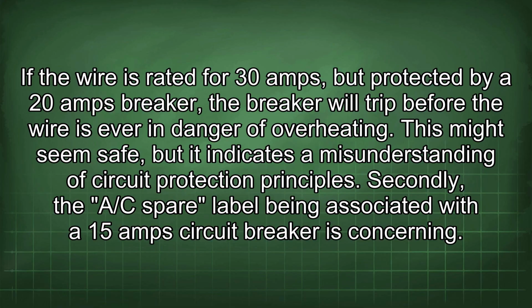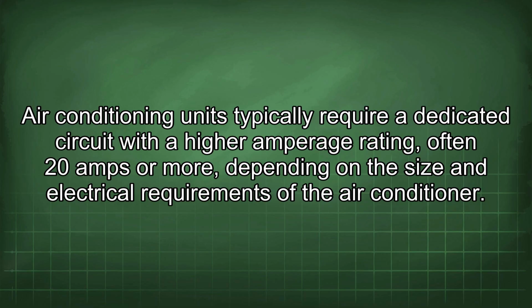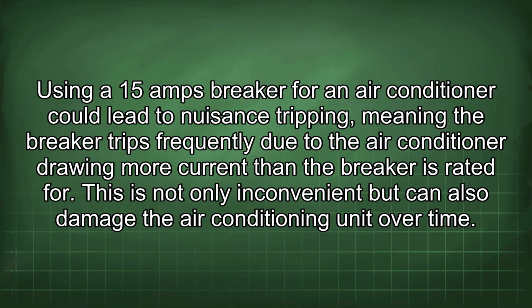Secondly, the A/C spare label being associated with a 15 amp circuit breaker is concerning. Air conditioning units typically require a dedicated circuit with a high amperage rating, often 20 amps or more, depending on the size and electrical requirements of the air conditioner. Using a 15 amp breaker for an air conditioner could lead to nuisance tripping, meaning the breaker trips frequently due to the air conditioner drawing more current than the breaker is rated for. This is not only inconvenient, but can also damage the air conditioning unit over time.